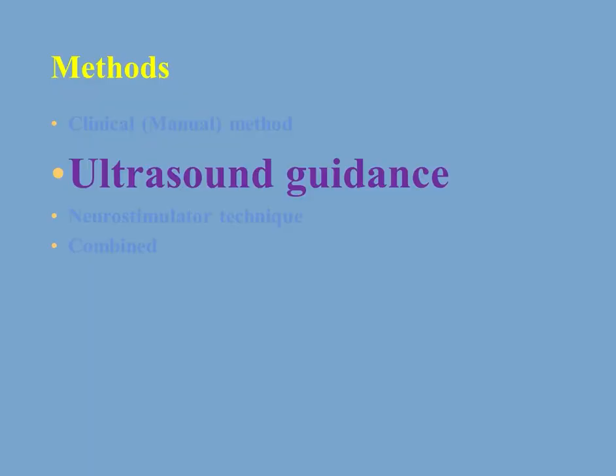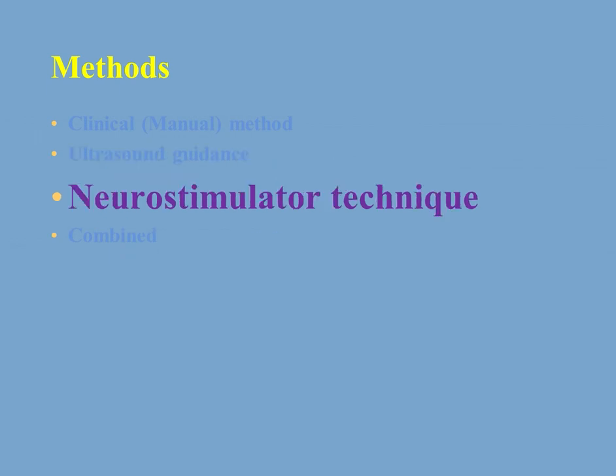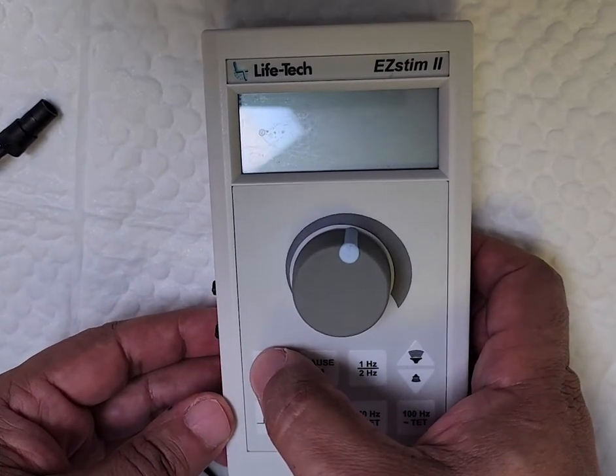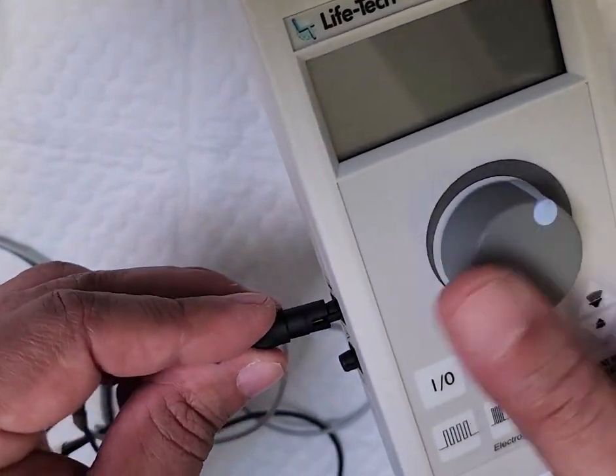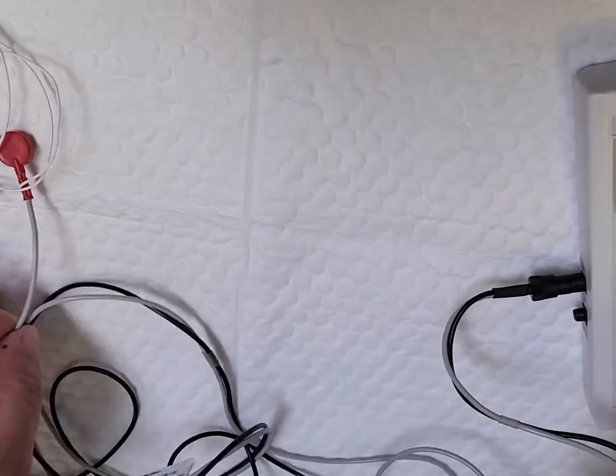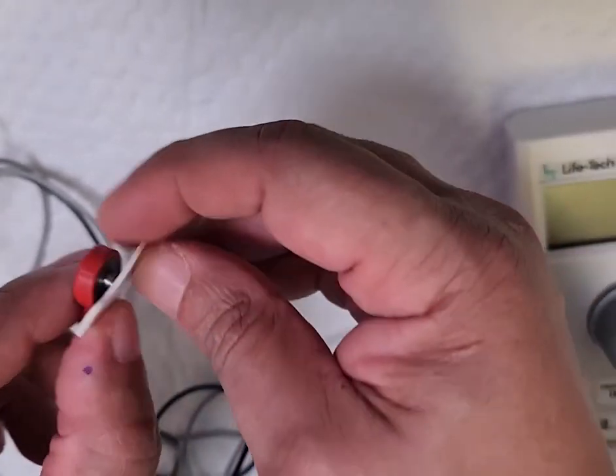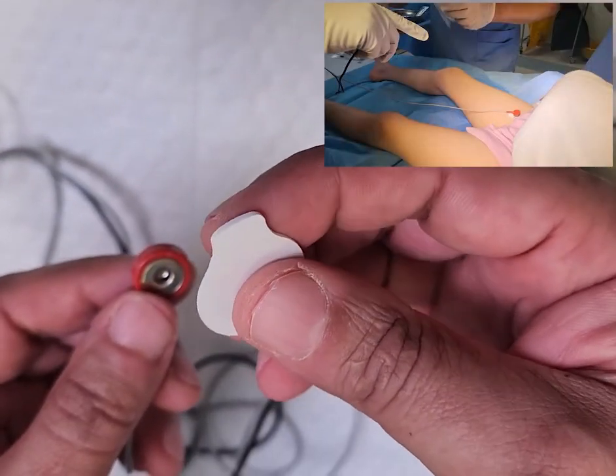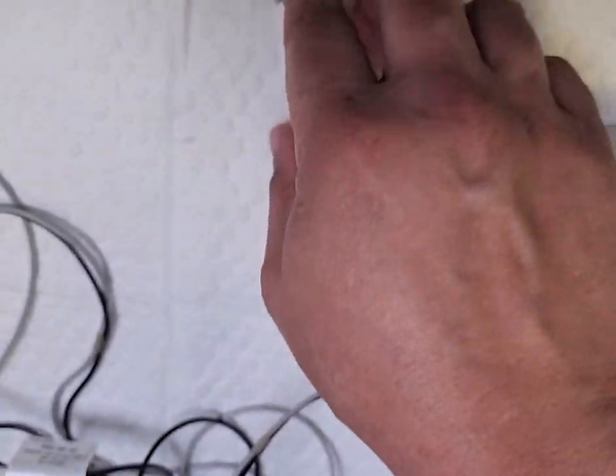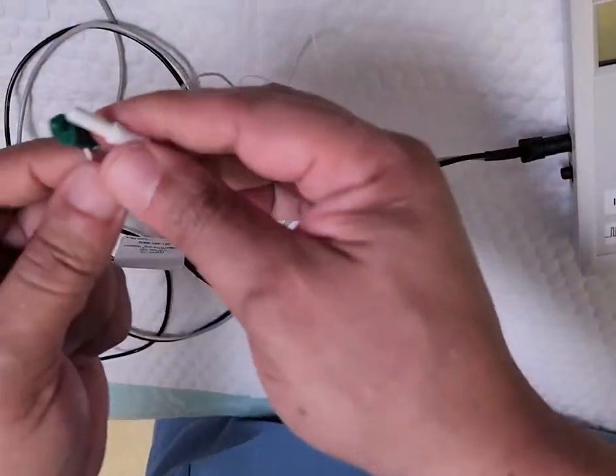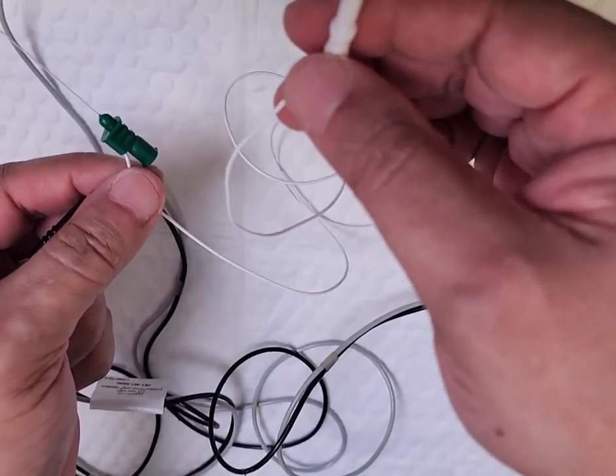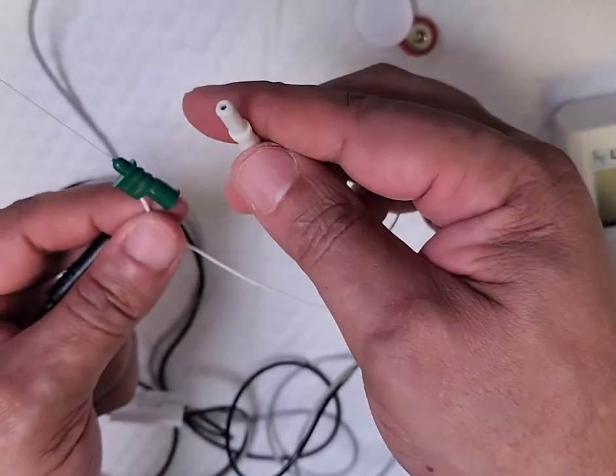The problem with the ultrasound guidance method is the difficulty in identifying small muscles when they are compacted together, as in the forearm. That's why the neurostimulator method has an extra advantage. In this method, we use a neuromuscular stimulator — there are many commercially available, like this one from Lifetech. It has two electrodes: the red one attaches to an ECG sticker on the child's skin, and the other electrode attaches to a special needle used both to stimulate the muscle and to inject the botox.